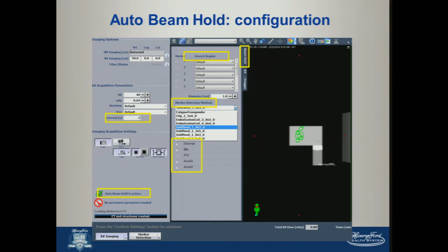So this becomes a bit clearer. This is how you would set it up at the console. You've got a number of options to choose. The frequency with which these images are taken, so I think the minimum interval is 3 seconds. You can specify a search region, and I'm not sure of what the options there should be. You can specify a marker detection method which might be optimized for a particular type of implanted marker you're using, so gold seed is highlighted here, for example. And then you can specify the kind of regions that you want to keep the markers within.